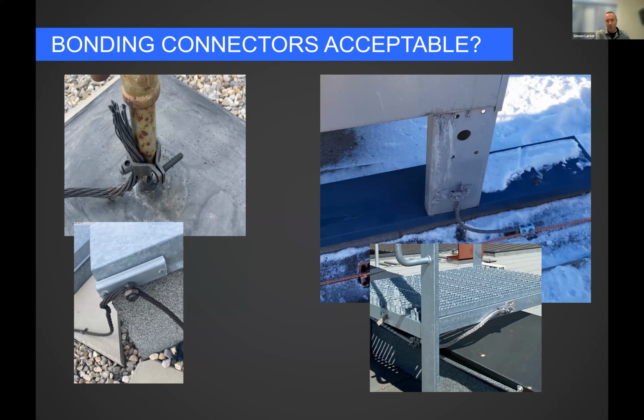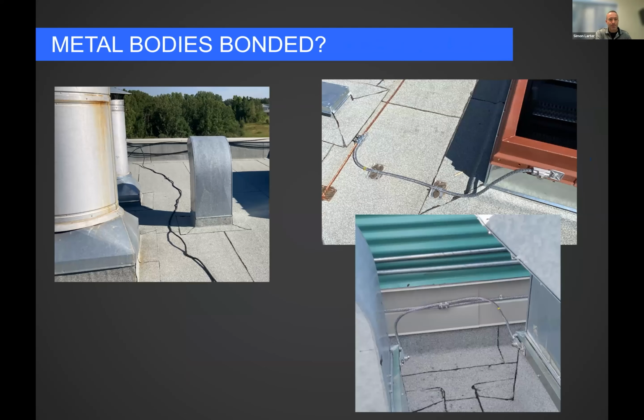Split bolts, we never use because they're usually not big enough for our stuff, and you have to squish our conductor to get them in. Are the metal bodies bonded at all? There goes the roofer special on the left. They just course the cable right between all those metal bodies, some of which are metal bodies of conductance and should have lightning protection on them, but do not now.